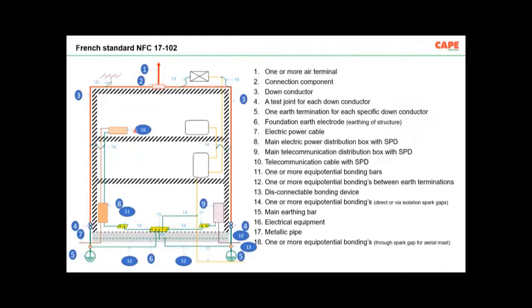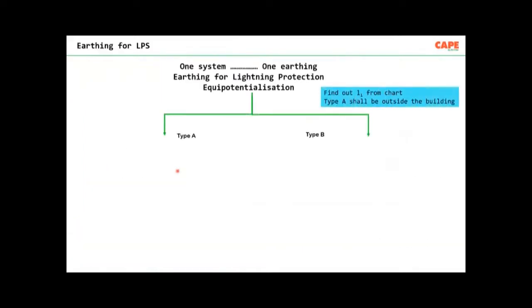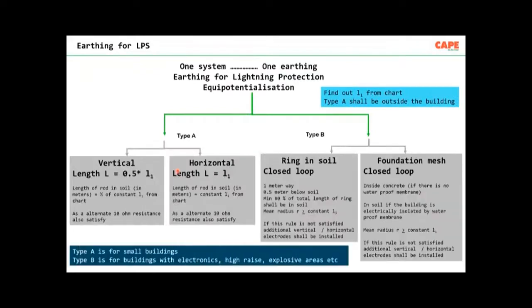This picture is actually from the French code. It says you are supposed to make a perfectly equipotential bonded system. Over and above, you can have an ESE rod. This is what it says. But the ESE manufacturer will never talk about this equipotential bonding. They always talk about one rod protecting 100 meters. This is wrong. Now, earthing of lightning protection is carried out in two ways, type A and type B.